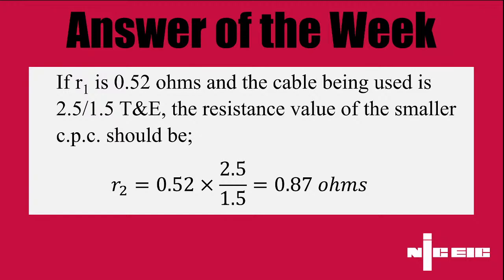Now what that means is there's a correlation or difference between your 2.5 resistance and your 1.5 resistance, and you multiply the little R1 by 1.67, and that should give you the likely or intended value of your end-to-end test result of your CPC, which equates to about 0.87. Now, for some of you that might be doing 4 mil ring circuits, that value is different, so we probably hear of the 1.67 multiplier. On a 4 mil/1.5 ring, it's actually 2.67, so it's slightly higher.